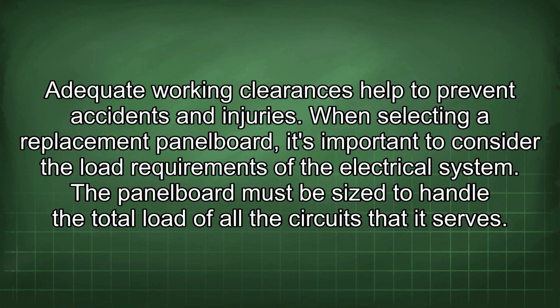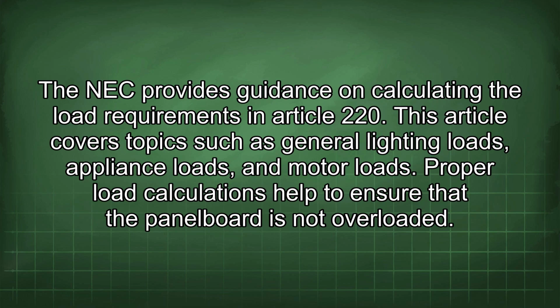When selecting a replacement panel board, it's important to consider the load requirements of the electrical system. The panel board must be sized to handle the total load of all the circuits that it serves. The NEC provides guidance on calculating the load requirements in Article 220. This article covers topics such as general lighting loads, appliance loads, and motor loads. Proper load calculations help to ensure that the panel board is not overloaded.